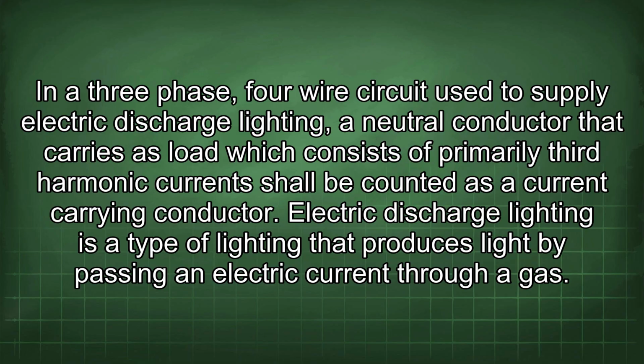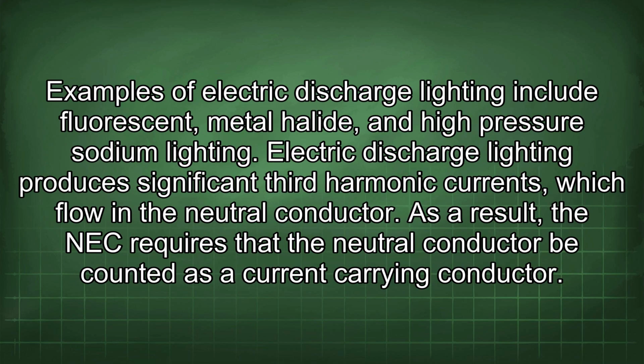In a 3-phase, 4-wire circuit used to supply electric discharge lighting, a neutral conductor that carries a load which consists of primarily 3rd harmonic currents shall be counted as a current-carrying conductor. Electric discharge lighting is a type of lighting that produces light by passing an electric current through a gas. Examples include fluorescent, metal halide, and high-pressure sodium lighting. Electric discharge lighting produces significant 3rd harmonic currents, which flow in the neutral conductor. As a result, the NEC requires that the neutral conductor be counted as a current-carrying conductor.